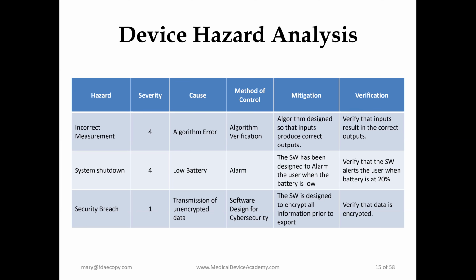So the verification activity, it doesn't have to be the actual written test. You can include a link to the verification testing document or a test ID that was done. But this is what they generally want to see for hazard analysis. And it also doesn't necessarily all have to be in one table. If you want to have your hazard analysis and then link your hazard ID to your verification in a different location, then you can do that. There's multiple ways to communicate the same information.